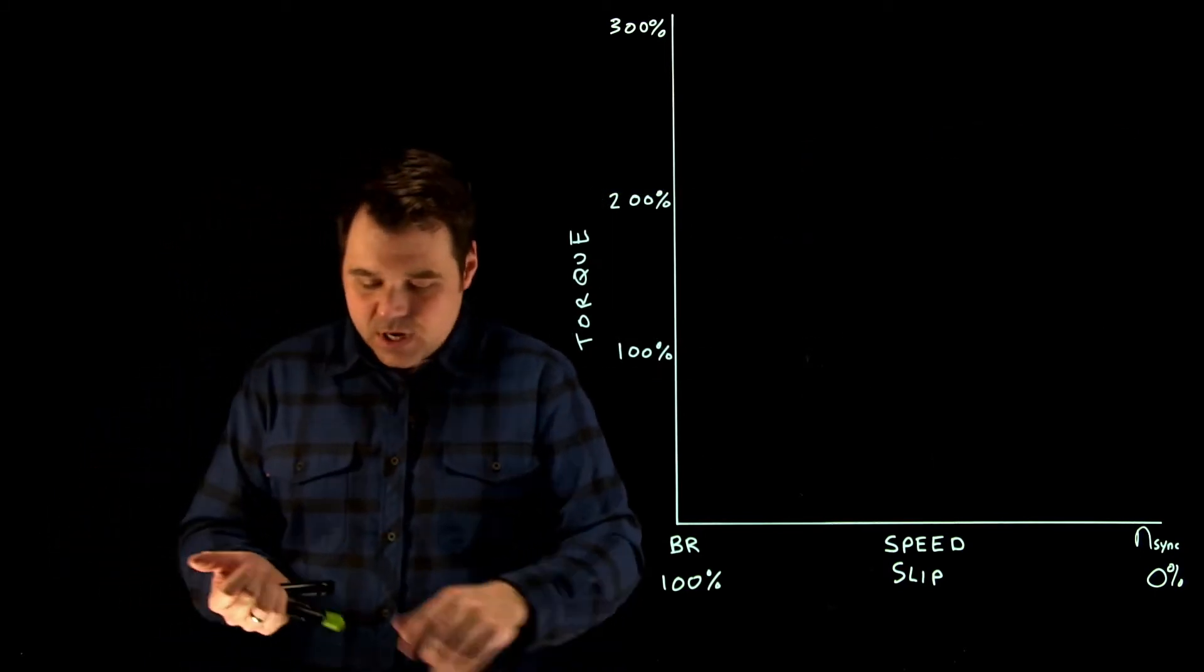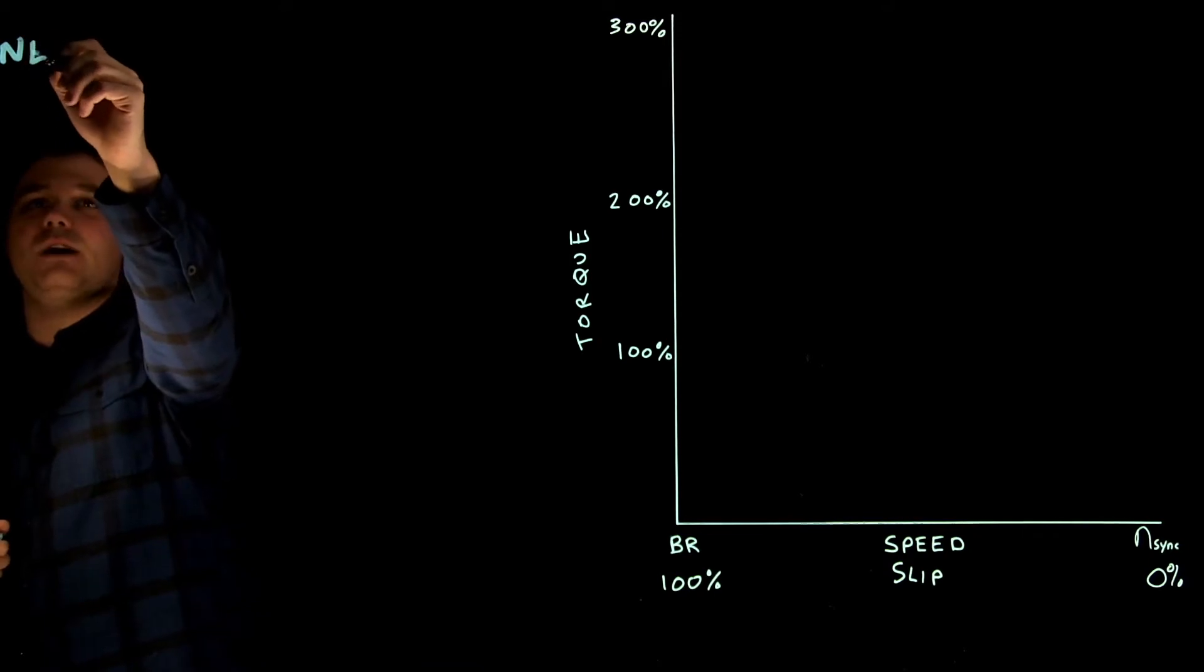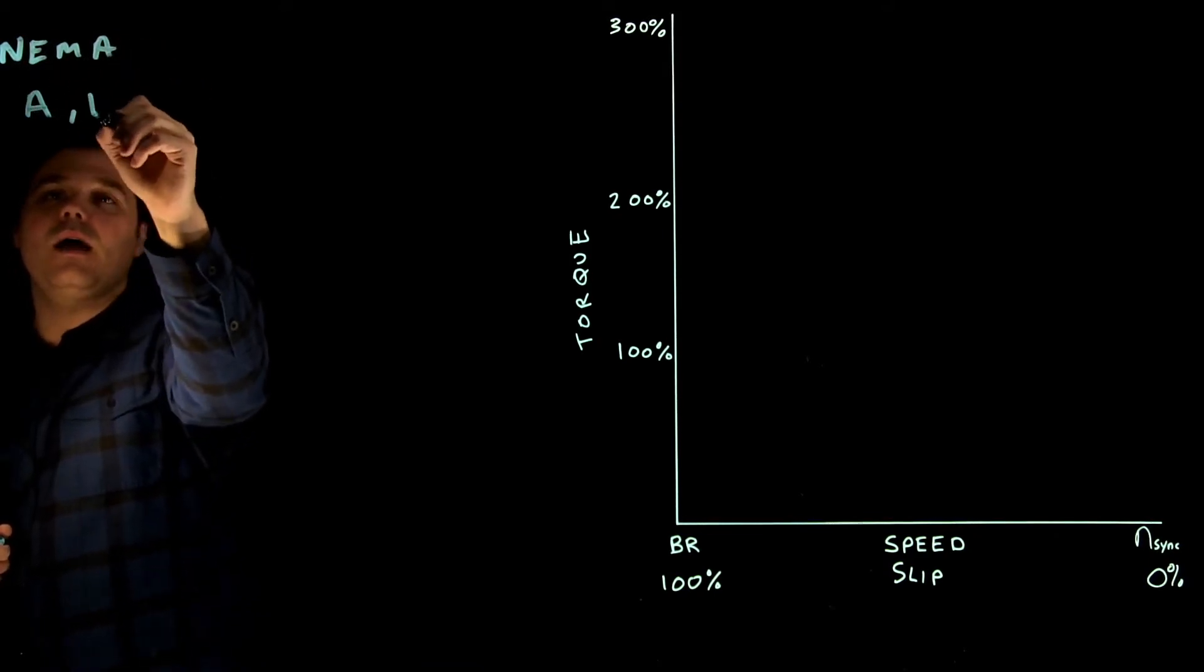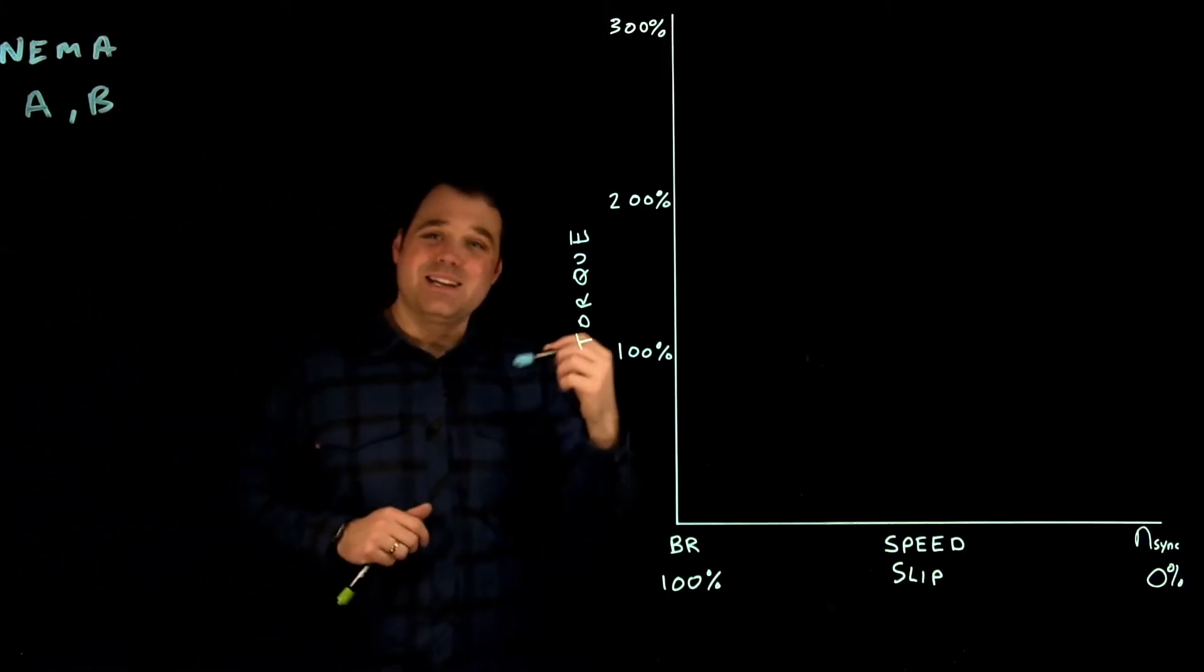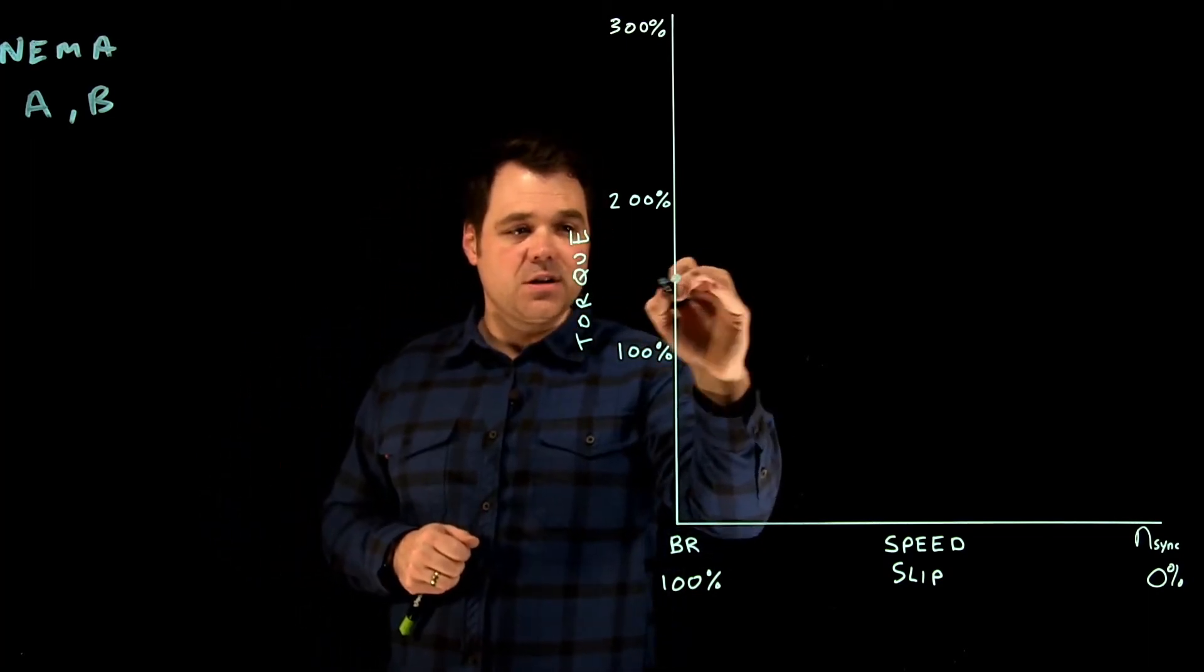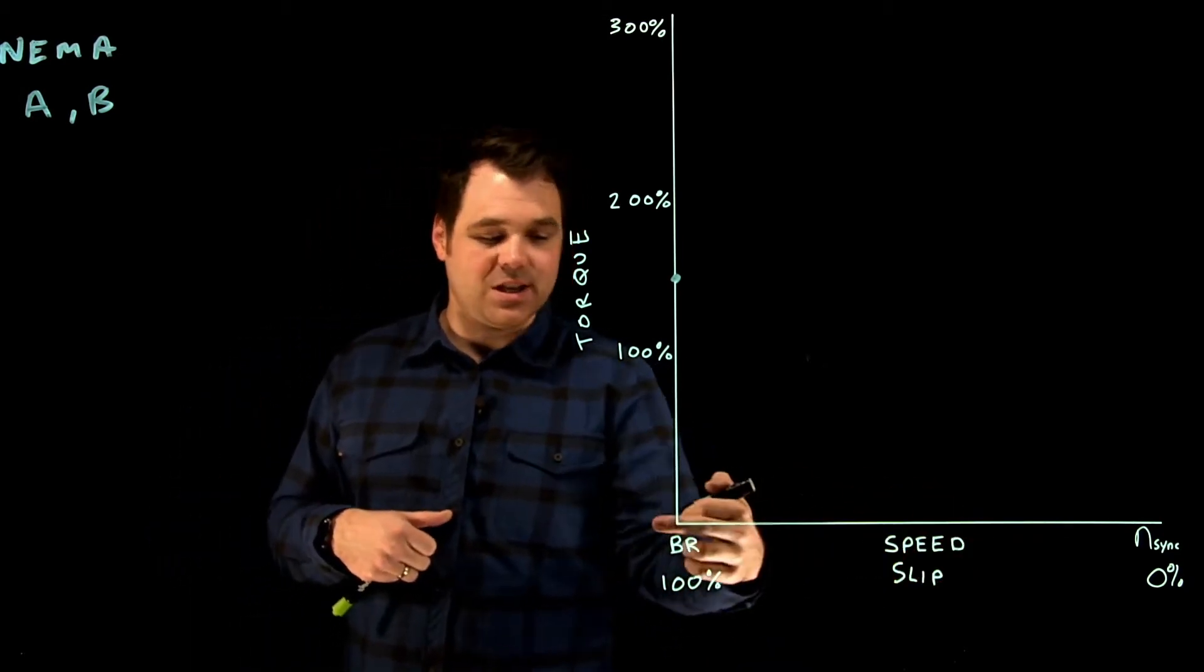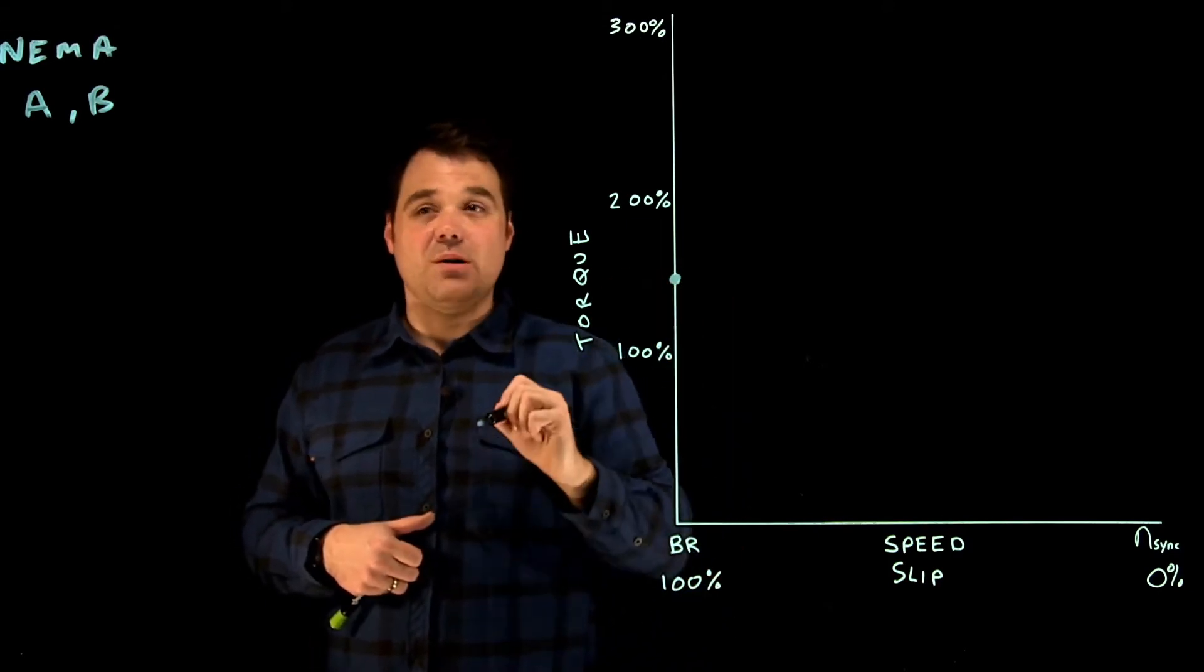So first off, NEMA design A and design B. These are all our NEMA designs. NEMA A and B operate pretty much identically. They both have about 150% starting torque, which would be at a blocked rotor when my speed is at zero or my slip is at 100%. That would be at start.